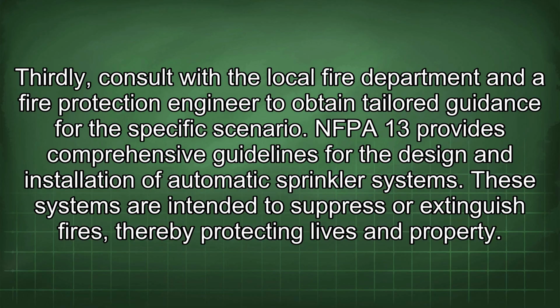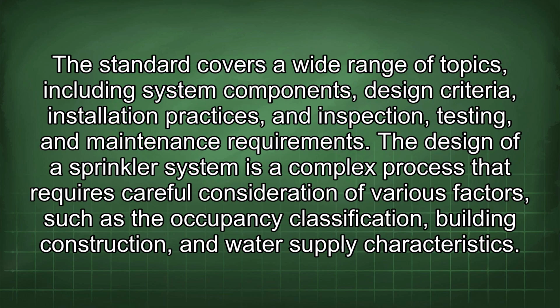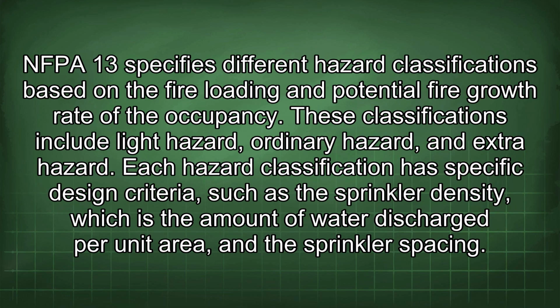These systems are intended to suppress or extinguish fires, thereby protecting lives and property. The standard covers a wide range of topics, including system components, design criteria, installation practices, and inspection, testing, and maintenance requirements. The design of a sprinkler system is a complex process that requires careful consideration of various factors, such as the occupancy classification, building construction, and water supply characteristics. NFPA 13 specifies different hazard classifications based on the fire loading and potential fire growth rate of the occupancy. These classifications include light hazard, ordinary hazard, and extra hazard. Each hazard classification has specific design criteria, such as the sprinkler density, which is the amount of water discharged per unit area, and the sprinkler spacing.